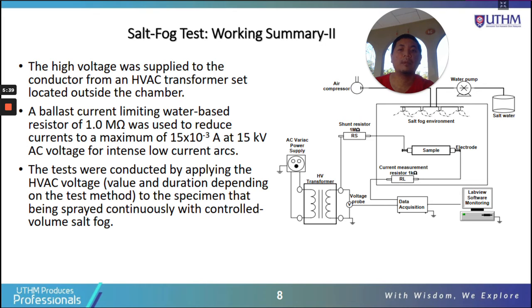So the tests were conducted by applying the HVAC voltage, high voltage AC supply. The value and duration of the voltage depend on the test method. Test method means it depends on the standard. We have to refer to the standard: how long is the duration of the test, and what is the value of the high voltage to inject on the sample? We have to refer to the standard, ASTM standard, for example, or IEC standard. The specimen is sprayed continuously with a controlled volume of salt fog. Even the volume of salt fog must be controlled, so we have to refer to the standard for that.